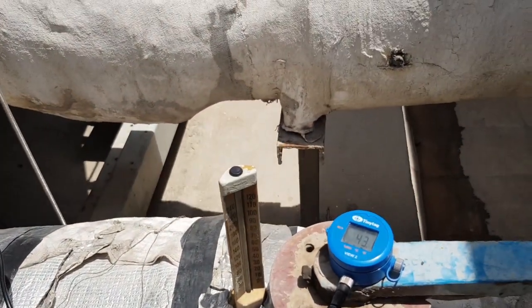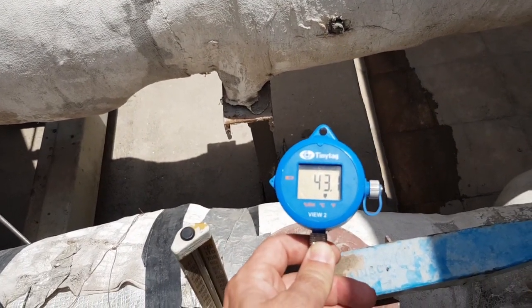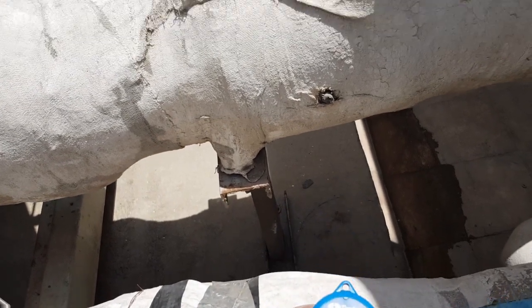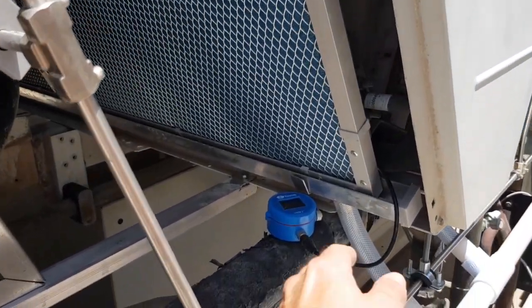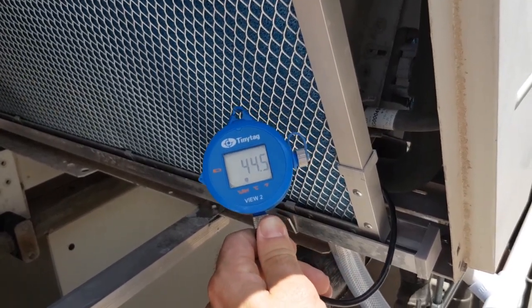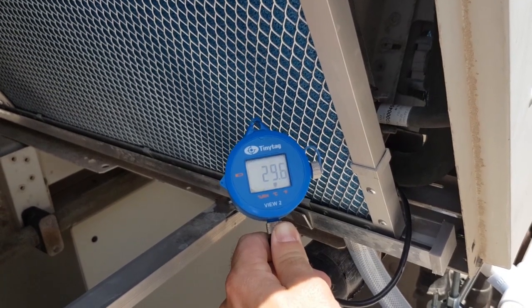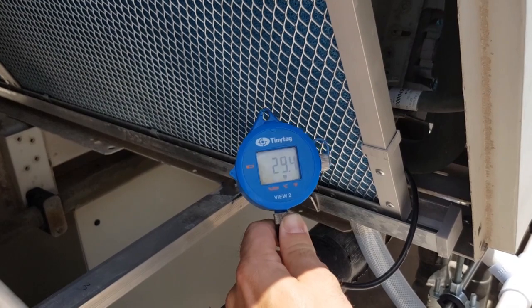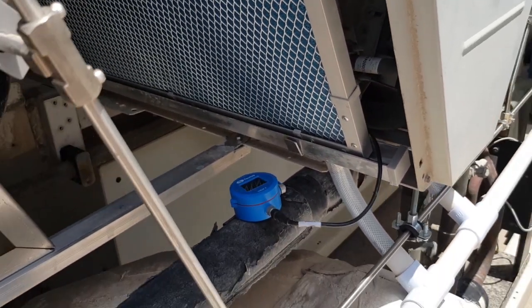The first probe measures ambient temperature: 43 degrees Celsius and 16% relative humidity. The probe after the membrane shows 44% humidity and 29 degrees Celsius entering air temperature — fluctuating between 27 and 29 degrees — so on average we are dropping down 14 degrees.